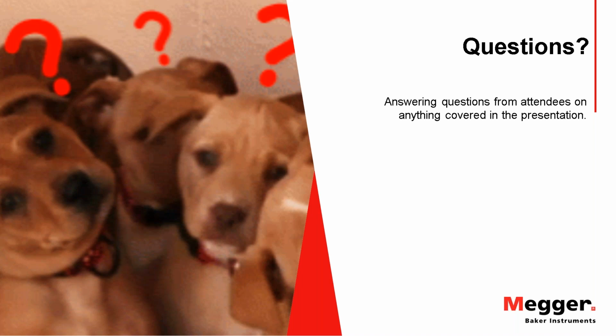Now, the downside, of course, is that the cables are involved. If the cables have low insulation resistance to ground, it's possible that all I'm really evaluating is the cables. Although when we do the surge test, we still evaluate the turn-to-turn insulation, so we can see that kind of weakness. The cables might mask the ground wall insulation readings or artificially lower PIs, because of the presence of contamination or moisture. If I'm testing cables, for example, that run through an underground cableway that's half full of water, that's obviously going to skew my results towards the lower, and it may not be an accurate representation of the motor. So we have to be mindful of understanding our specific installations and those specific challenges.